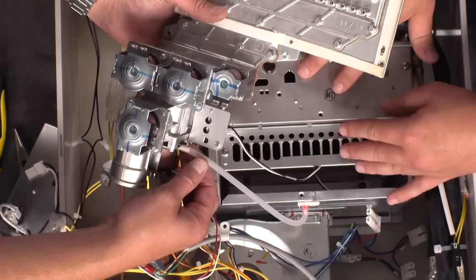One thing I'll show you in just a moment is a quick tip for putting them back together. Once you get it all unhooked, you'll want to take your hose off. This hose is there for the proportional valve to measure pressure. We're looking for a blockage in the heat exchanger and burners, and if we overpressurize because of a blockage while the fan's blowing, air pressure comes here and closes the diaphragm in that valve, preventing gas from going through. So it's a safety.